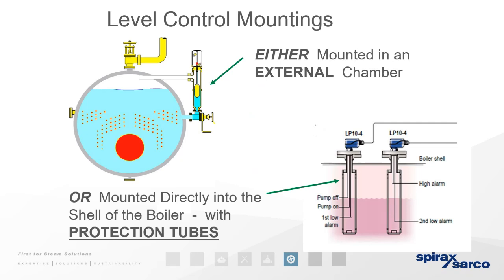So as it shows there, you've got your pump off, your pump on, first low alarm, and on a separate, because they need to be independent, you have your high level alarm, which is a choice. But the second low level alarm, again, is independent because it's on a separate probe, and should be mandatory, or is mandatory, to protect the fire tube on the boiler. Are there any questions at that point? No more questions, so we can proceed.